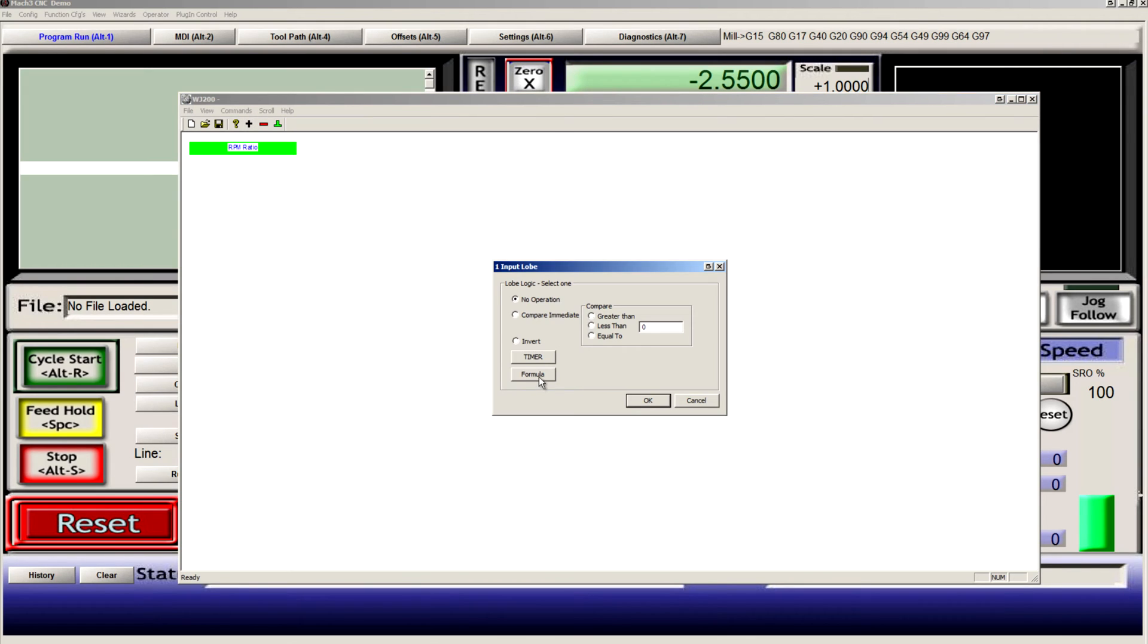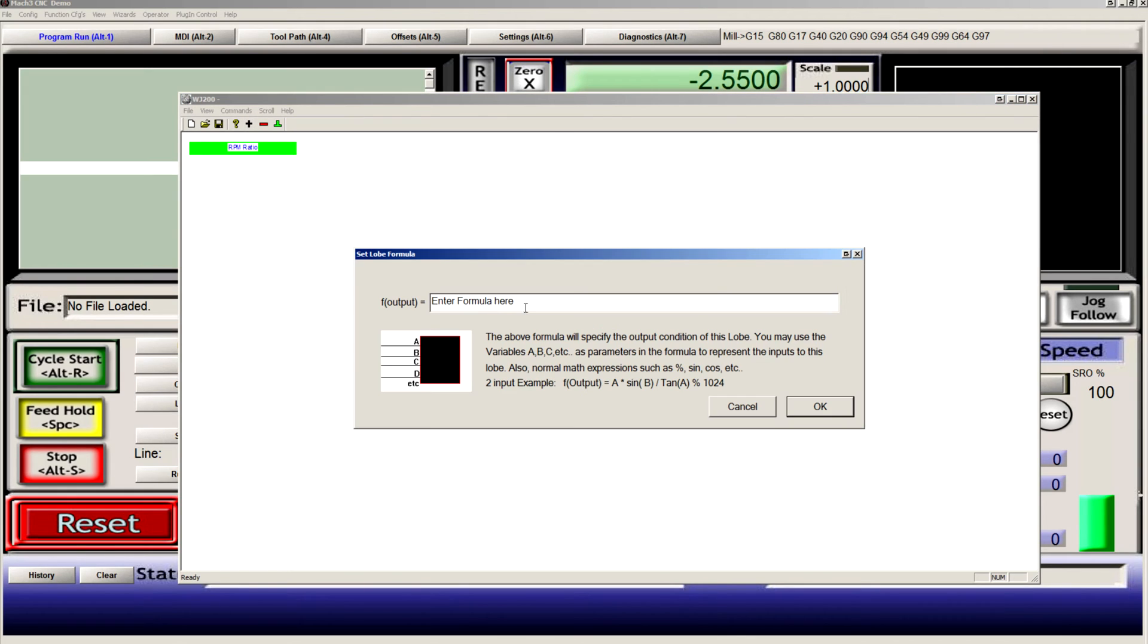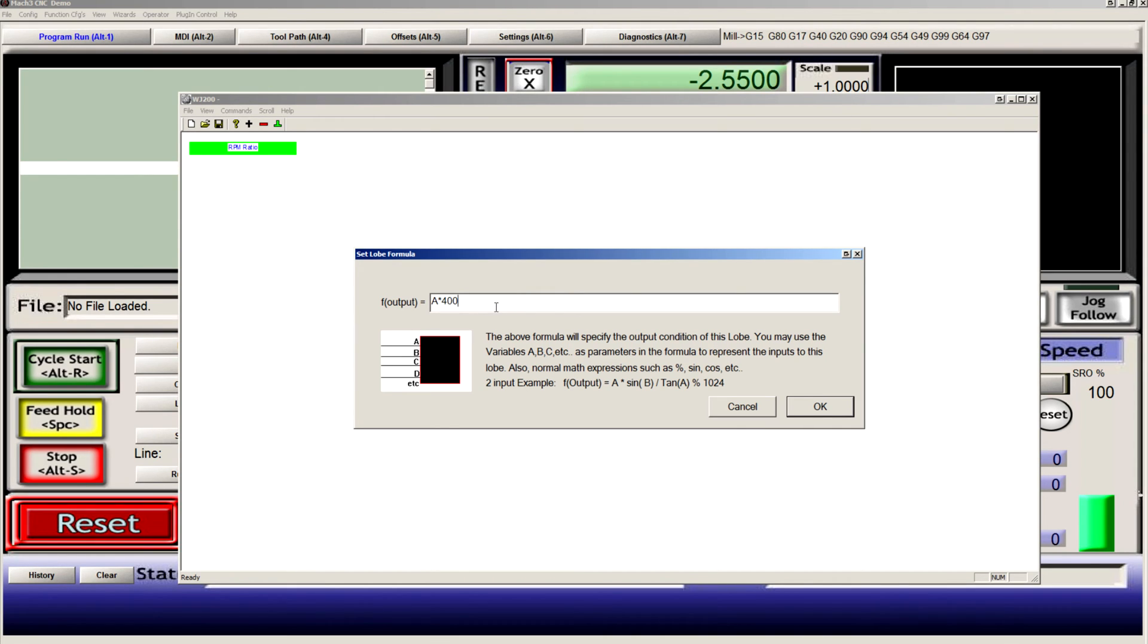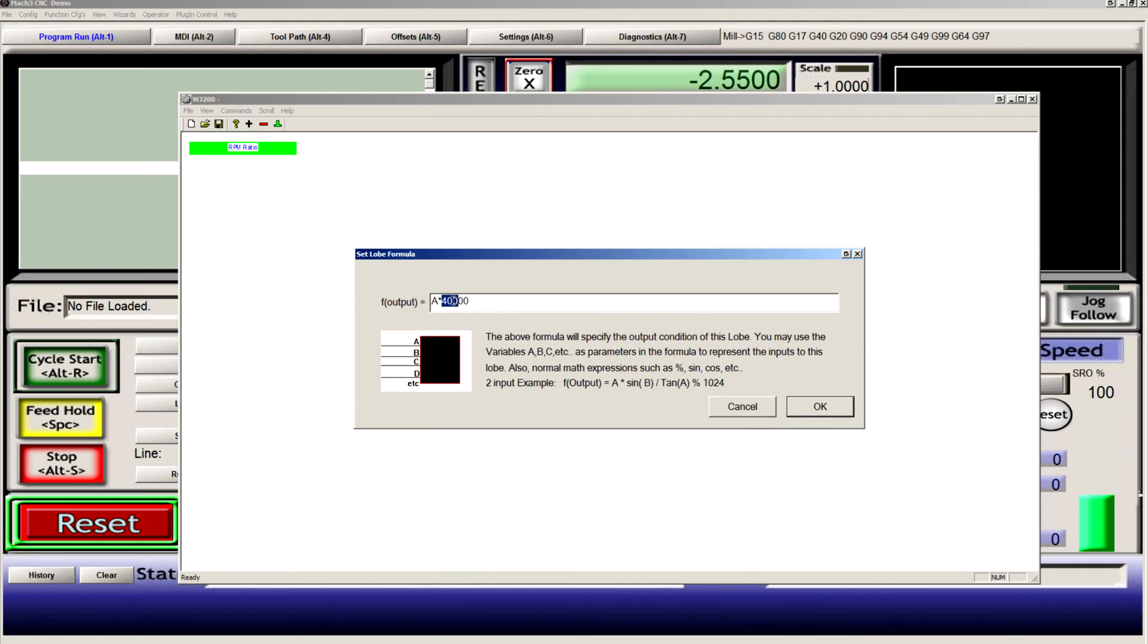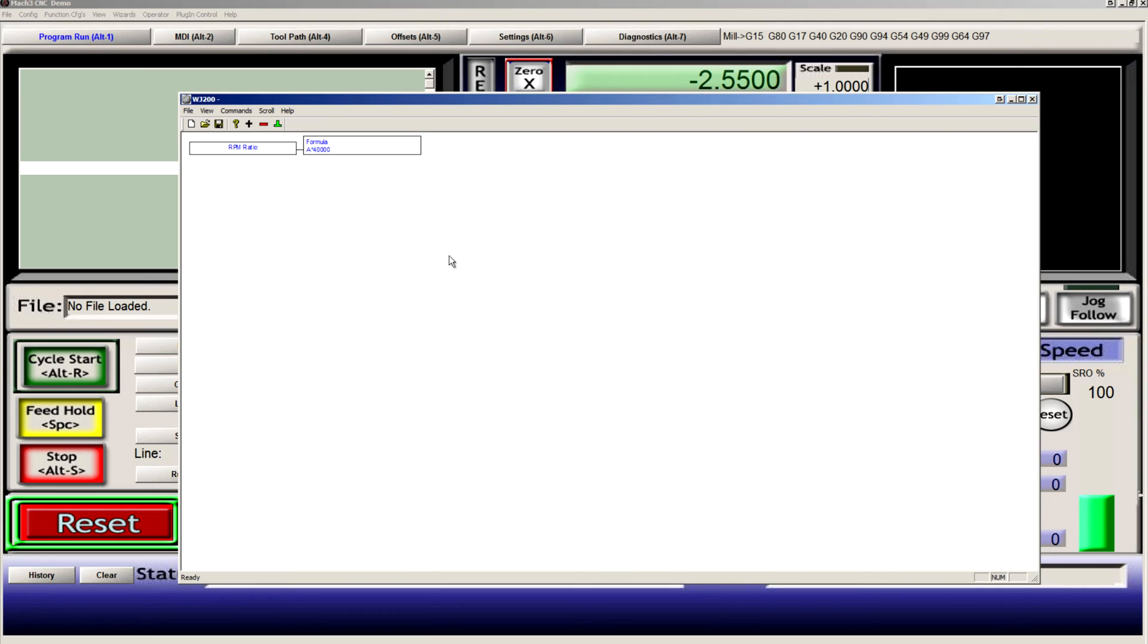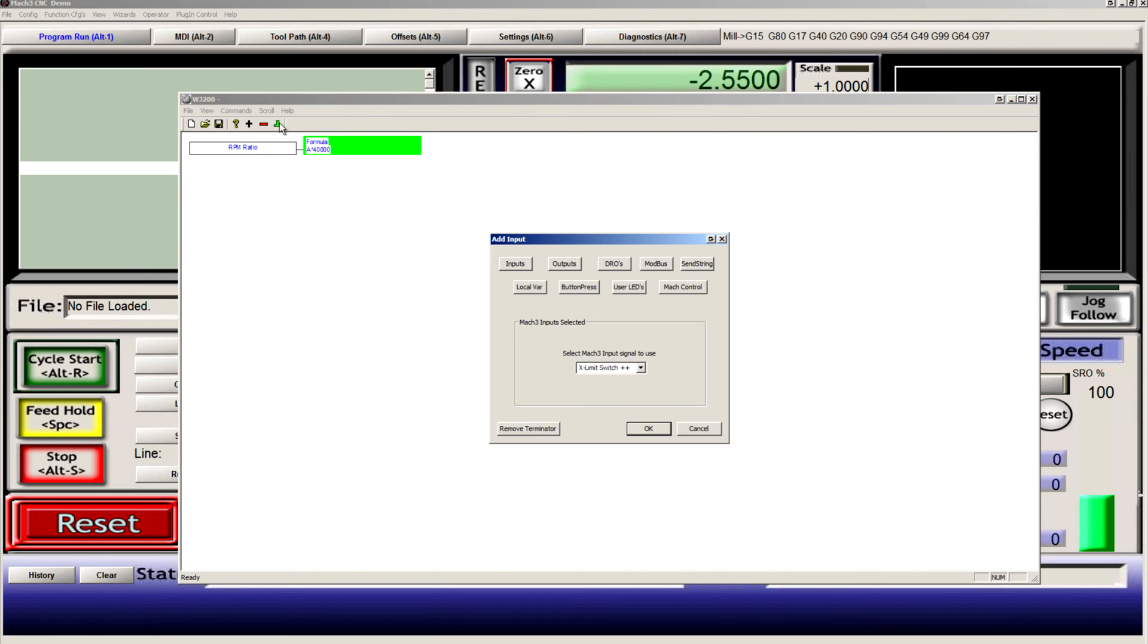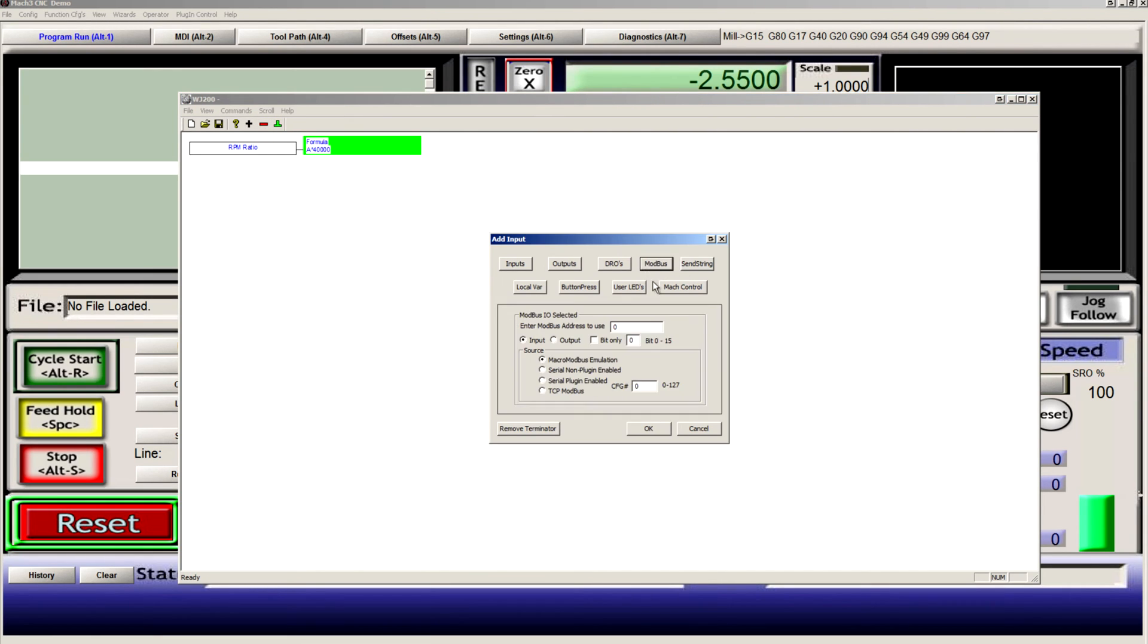Add a formula. Our ratio is A times 40,000. In this case, this is a 400 hertz spindle, and the VFD has 0.01 resolution on this setting. Terminate that to Modbus output serial plugin configuration 0.